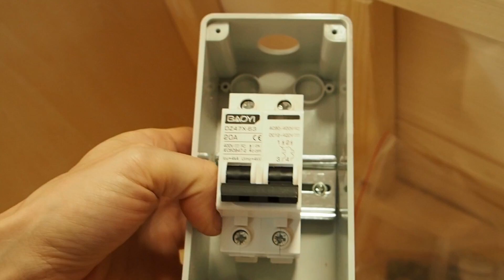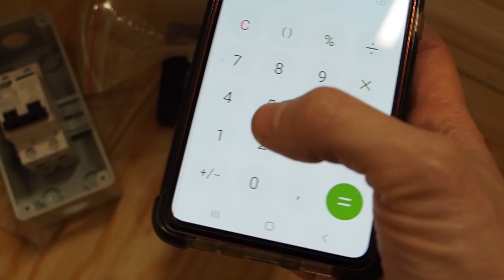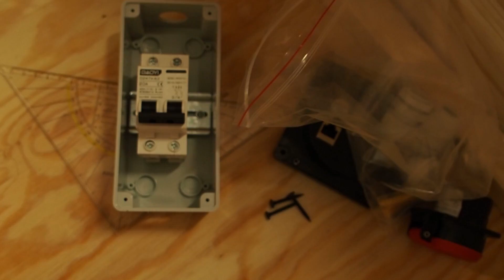In general, you should size your breaker, fuse, or any other safety device 25% bigger than the actual current coming in. So let's say we have 14 amps and multiply that by 25%. That's 17.5 amps, and the next bigger size breaker is 20, so it should be fine for our project.